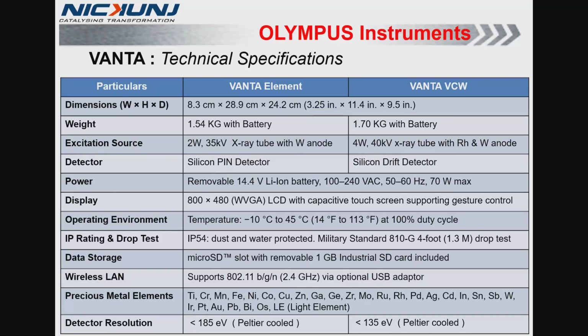As displayed, most of the specifications are common for both the variants. The dimension of the machine is 3.25 inches by 11.4 inches by 9.5 inches. The weight of Vanta Element is 1.54 kg with battery, and for Vanta VCW it is 1.70 kg with battery. The X-ray tube: Vanta Element has a 2-watt 35 kV X-ray tube, and Vanta VCW a 4-watt 40 kV X-ray tube. Vanta Element has a silicon PIN detector, while Vanta VCW comes with a silicon drift detector. Power requirement for both variants is the same, that is 230 volt AC, and power consumption is 70 watt max.